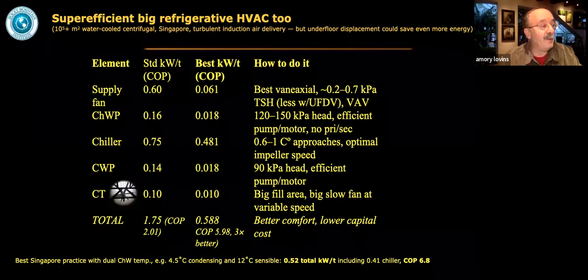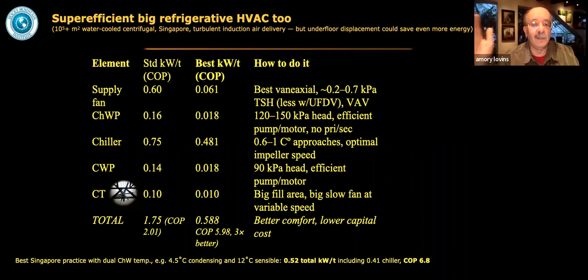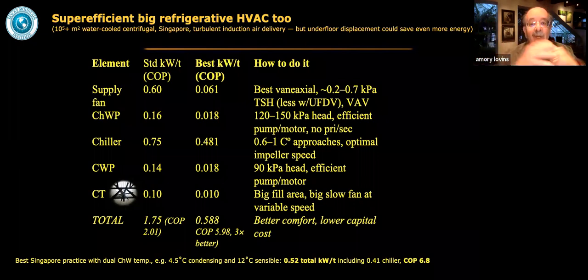Now, here's the same in metric units. If you do nonetheless have a big water-cooled centrifugal chiller system, here's how Mr. Lee does that. And COP is the amount of cooling you get per unit of electricity. So his end-to-end supply fan through cooling tower system COP at the Singapore design hour, one of the world's toughest climates, is 6.8 with or 6 without the dual chilled water temperature.